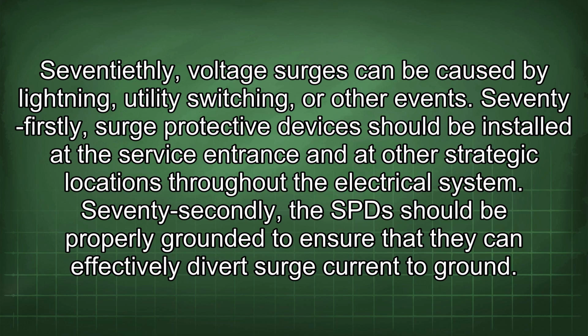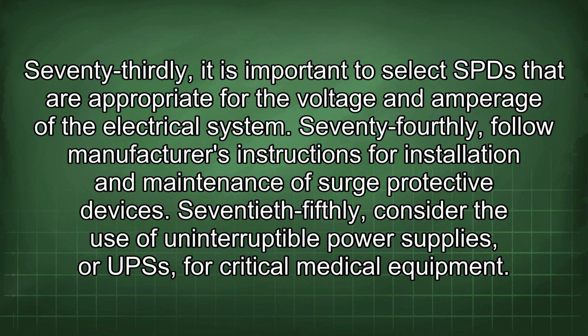71st, surge protective devices should be installed at the service entrance and at other strategic locations throughout the electrical system. 72nd, the SPDs should be properly grounded to ensure that they can effectively divert surge current to ground. 73rd, it is important to select SPDs that are appropriate for the voltage and amperage of the electrical system. 74th, follow manufacturer's instructions for installation and maintenance of surge protective devices.